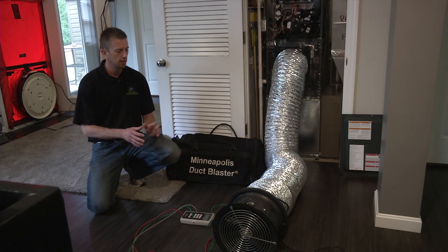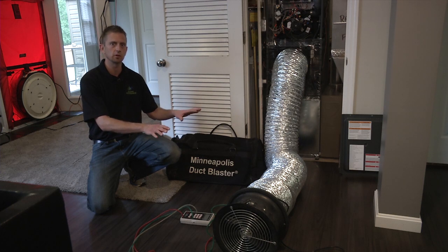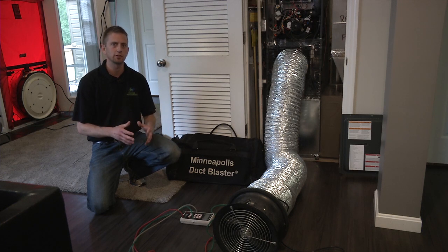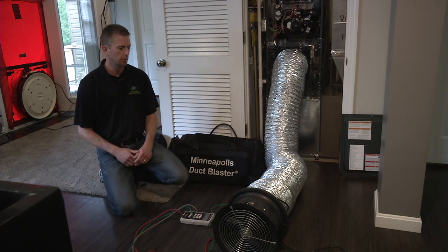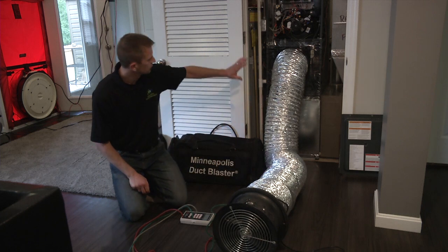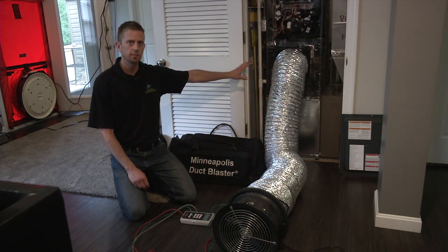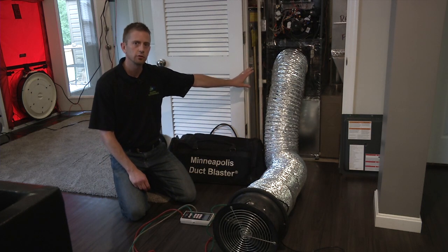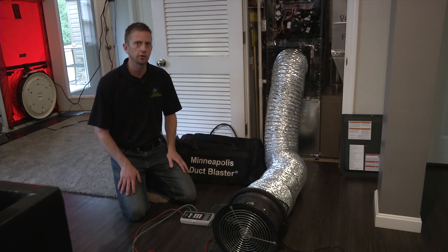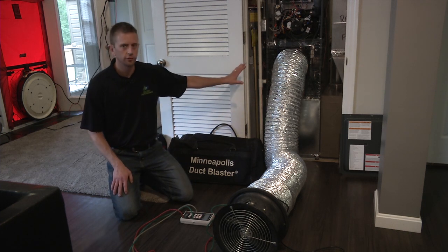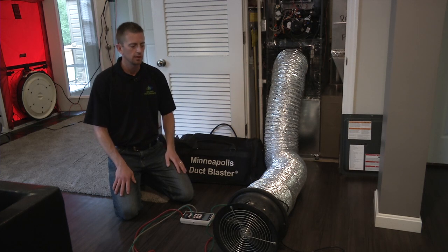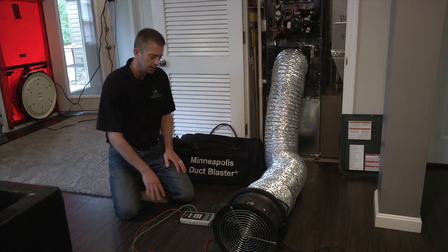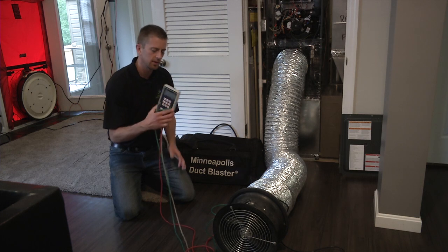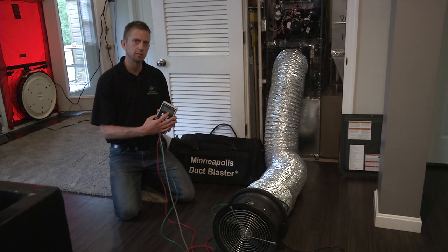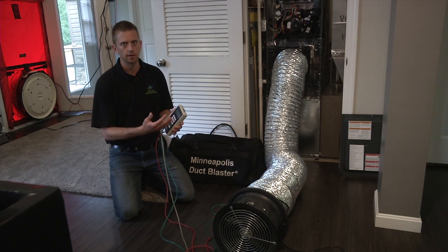You can do the total leakage test with just this piece of equipment, but if you want to do the duct leakage to outside test, you also need to use a blower door. Basically this connects to the furnace or the heat pump in your house. You can connect it directly to the air handler, or to a central return in the house. I prefer to connect it directly to the air handler. So this is the Duct Blaster. It has a pressure gauge that comes with it. This tells me what the pressure in the duct system is, along with the leakage numbers that I'm looking to get.